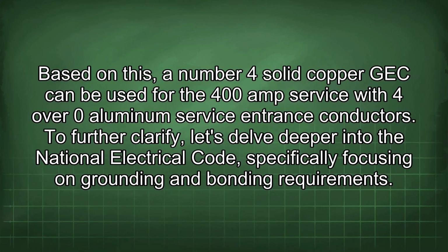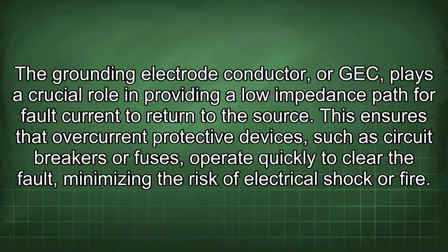To further clarify, let's delve deeper into the National Electrical Code, specifically focusing on grounding and bonding requirements. The grounding electrode conductor, or GEC, plays a crucial role in providing a low impedance path for fault current to return to the source. This ensures that overcurrent protective devices, such as circuit breakers or fuses, operate quickly to clear the fault, minimizing the risk of electrical shock or fire.